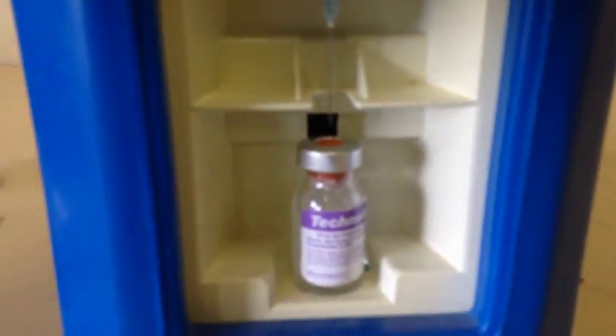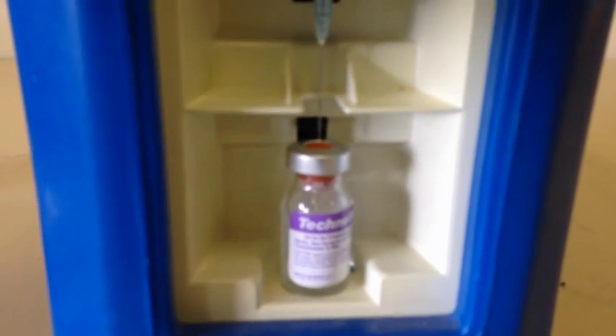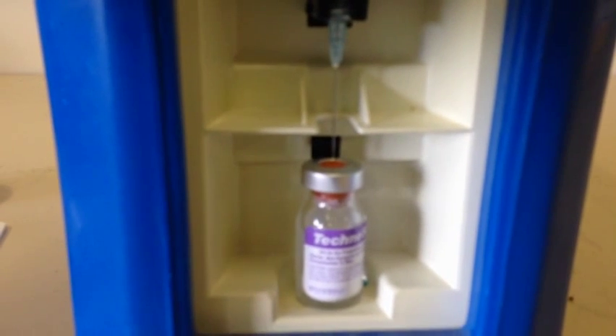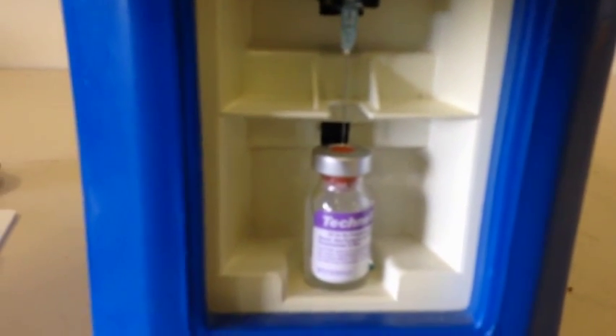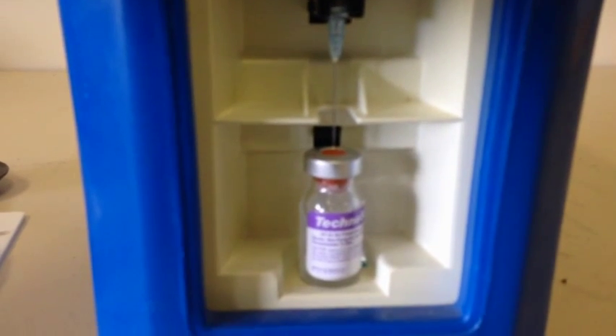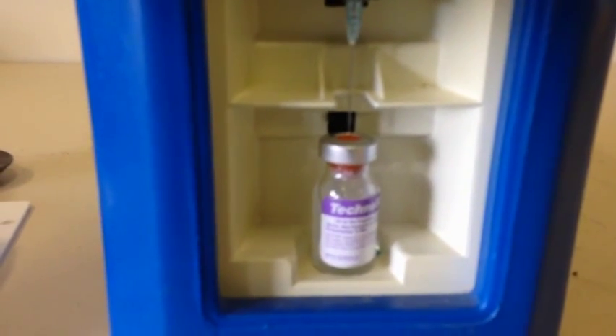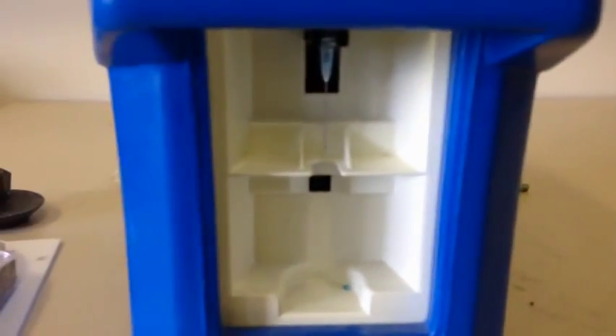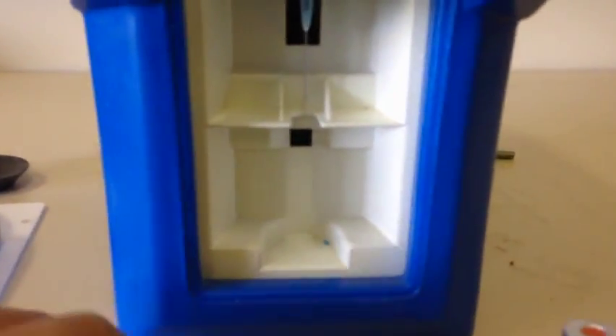There's a little tab here. We lift this tab, and as we lift the tab you can see the needle drops down and punches—in theory punches—the vial. It's an evacuated vial of, say, 20 mils. So it will draw 20 mils of saline out of the bag across the aluminum column and into that vial. So that's the actual mechanism.